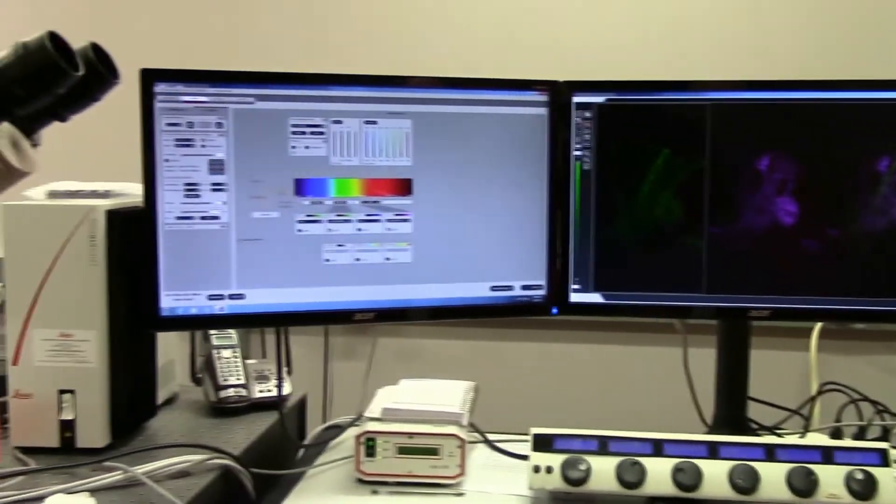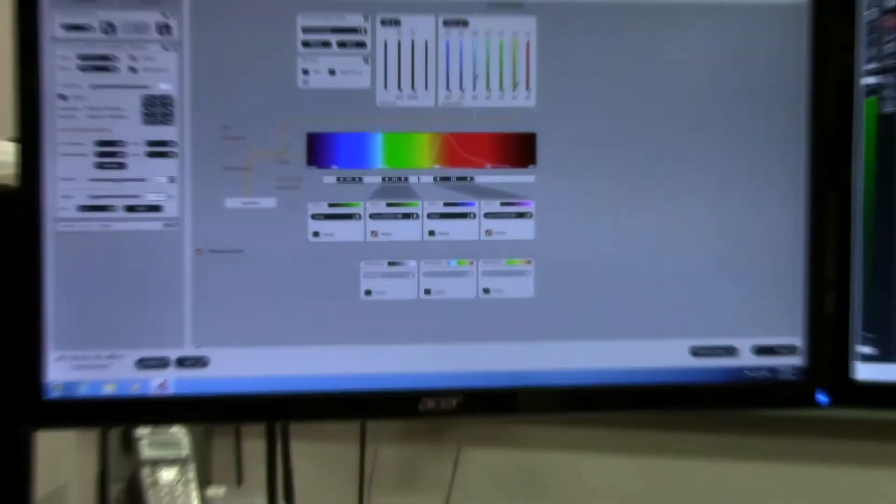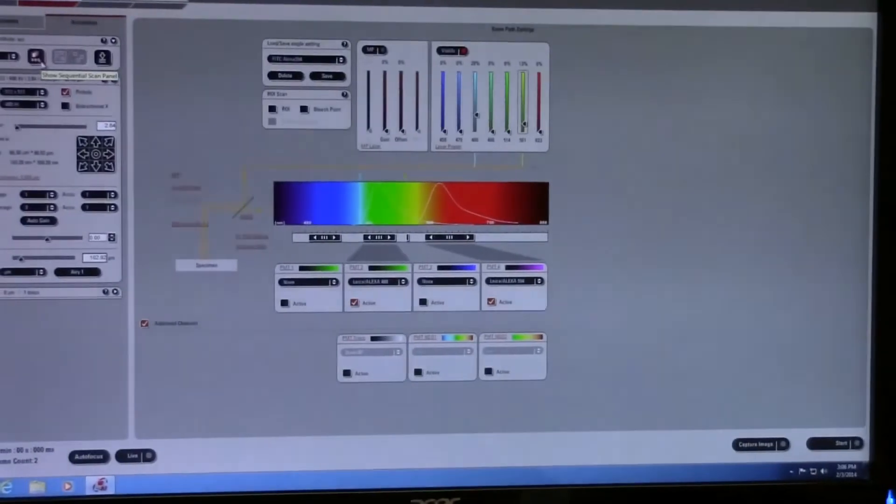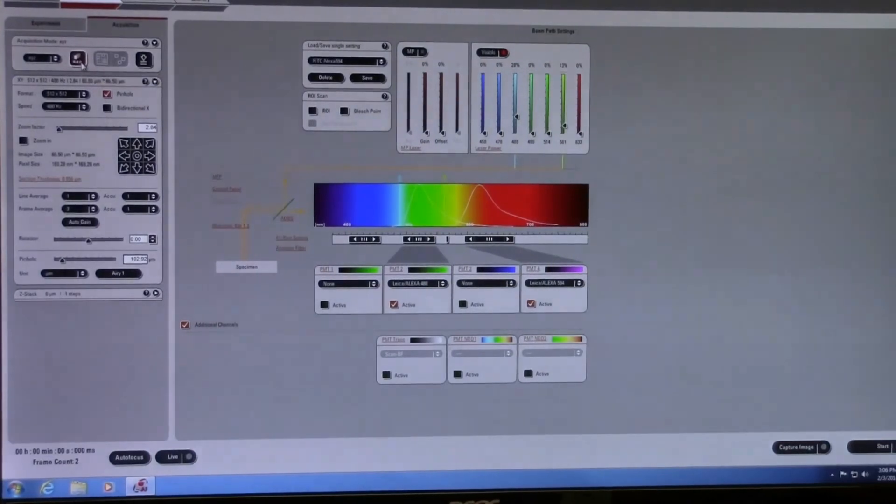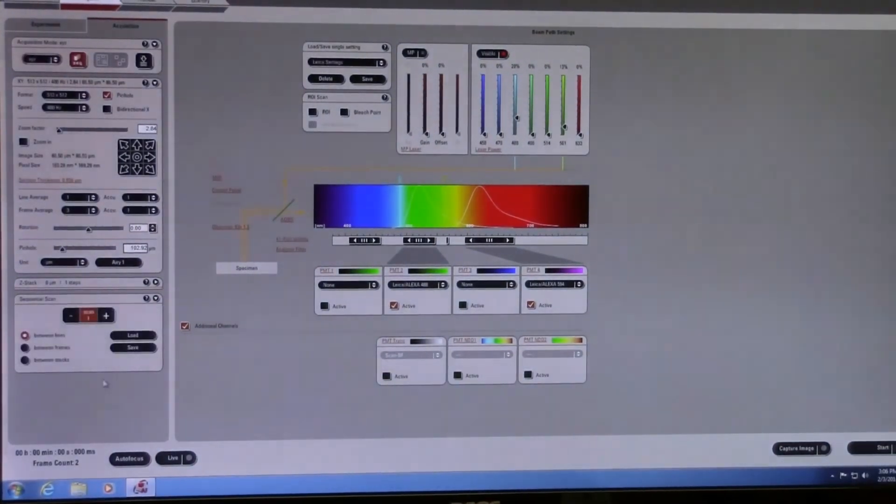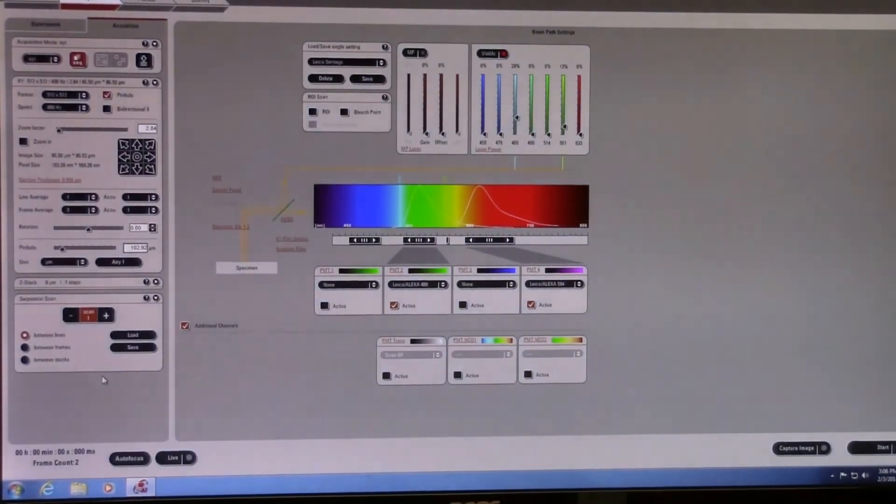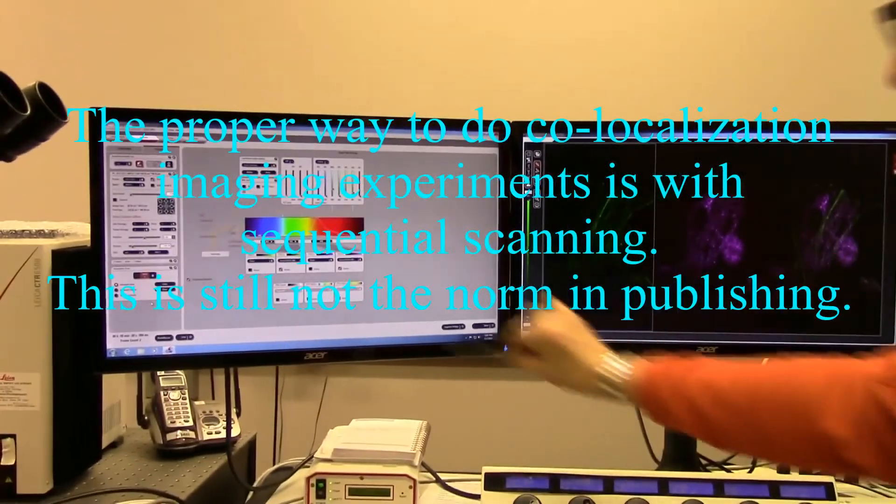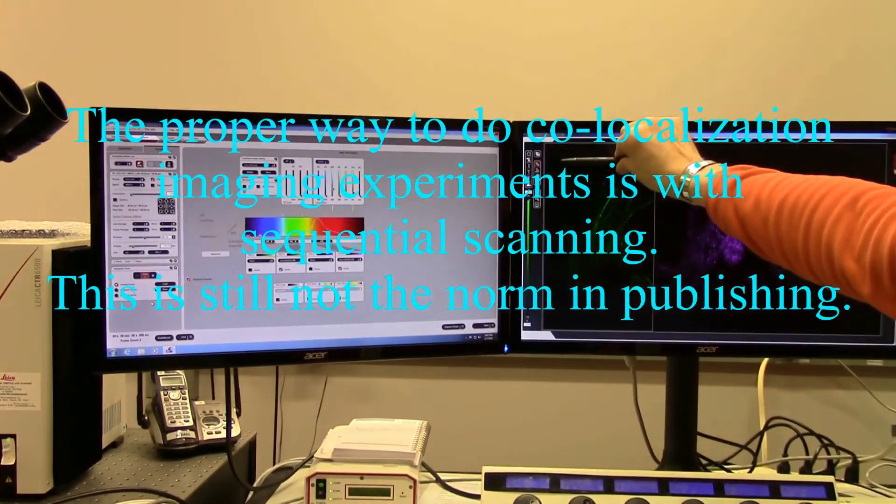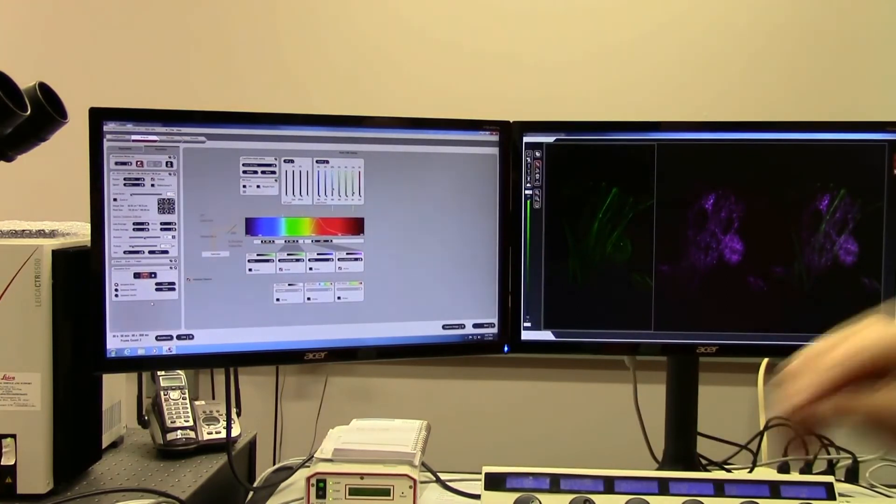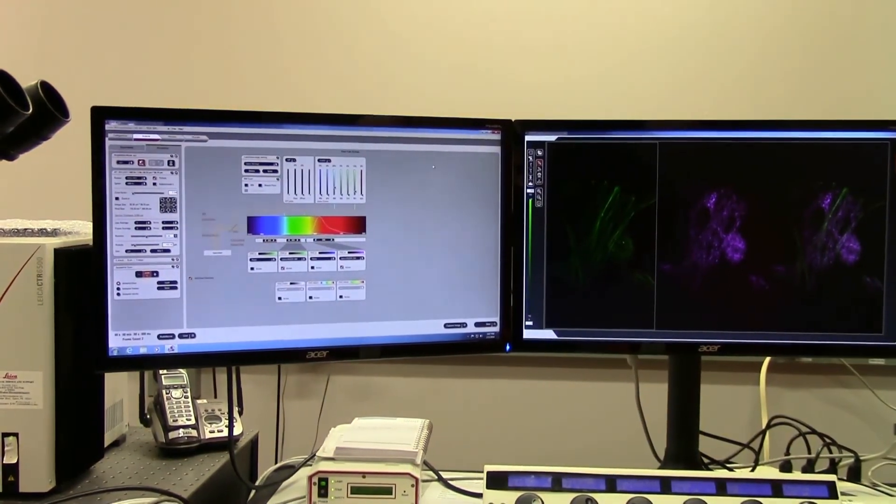If we look over now on the left-hand side, we'll see a button up here with SEQ, and that's to show the sequential scan panel. We can click that, and a new panel will appear. Now what we can do is we can do multi-channel scanning where instead of having both lasers or even three lasers on at the same time and spectrally getting distinct signals using the gating, we're in fact going to only scan with one laser and one gate and another laser and then another gate sequentially. The way this is done is by setting up the channels independently.